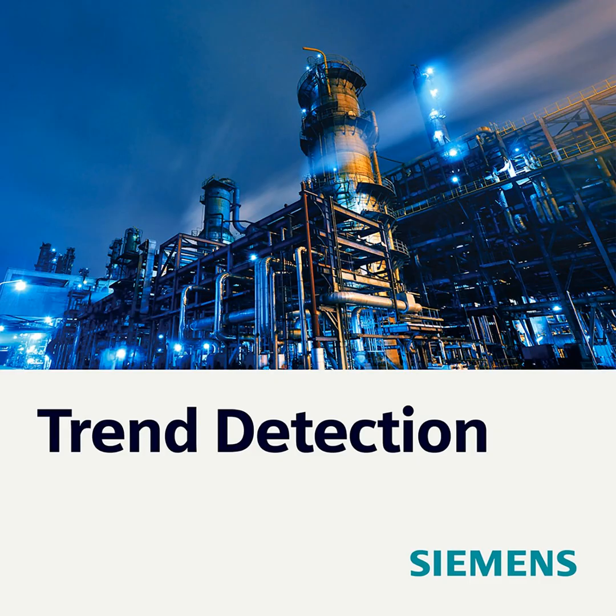So with the example, maybe I select all of this. I say 1, 2, 3, 4. These are the states that I would like to teach the system, teach the AI, that this is the normal operational state. We also have a field called training optimization, with which it also filters out the idle states a bit. So really to take only the applicable data, the valuable data, and ignore the idle states a bit.